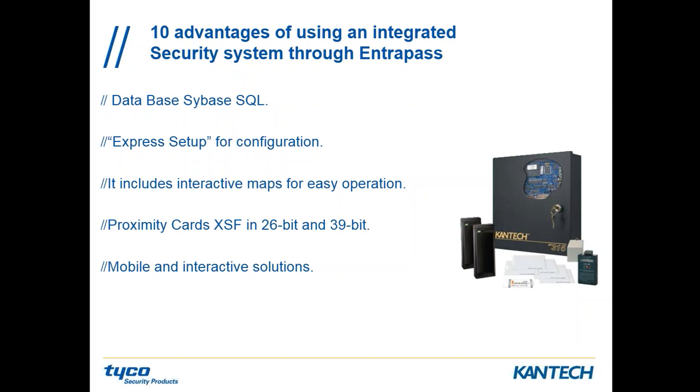It's not only being able to see the camera from your access control, or to see you have an intrusion alarm, or an alarm at your fire system, but we can link them together intelligently. Meaning if you have a zone in your DSC in alarm, we can program the access control area to have the siren going off. We can program it to have all the cameras in that area pop up automatically for the operator, so they don't need to go and look for which one.